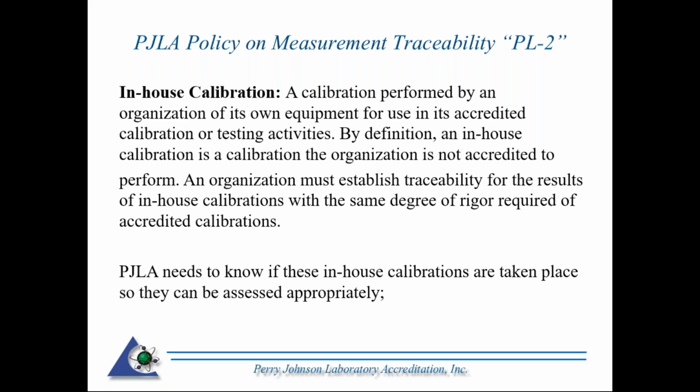One thing I want to highlight here is that if you are performing any in-house calibrations and you are accredited with us, we need to know about that before we come out and do the assessment. The reason being is 17025, we're looking at the technical competencies of the organization. So the assessor is going to have a background in the testing field you're in. So if you happen to be performing an in-house calibration, someone competent in that area is going to need to evaluate it.